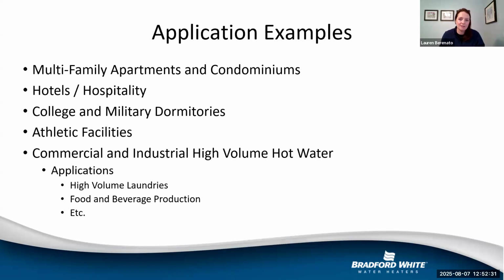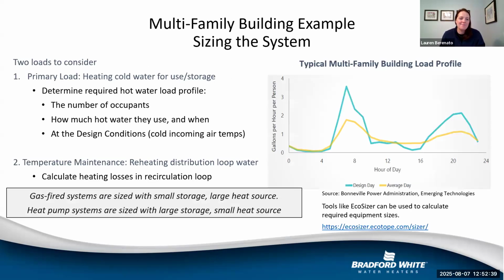So application examples, these are just a few examples that our team put together showing where a heat pump would operate for sizing. Two primary loads for a multifamily building example. Your primary load is for heating cold water for use and storage, and then also for temperature maintenance for reheating distribution loop water. So just kind of going into sizing protocols, which everyone on this call, if they're an engineer and designer, should be familiar with: determine the hot water requirement, occupants, how much water they use, design conditions, for example. And then you'll want to calculate the heat loss in the recirculation loop.